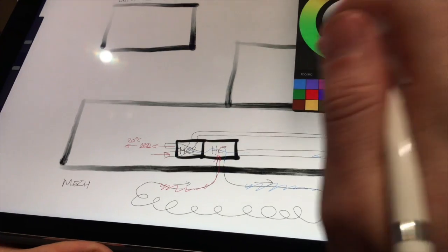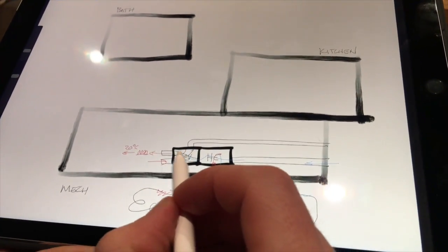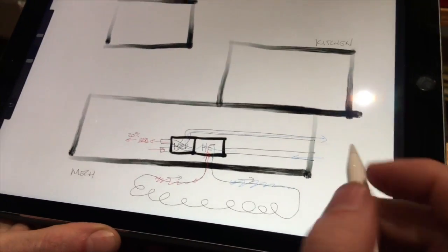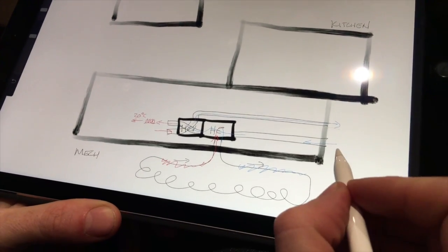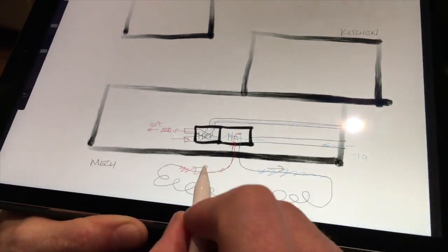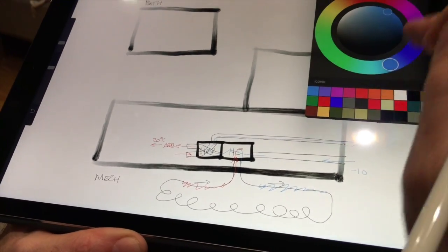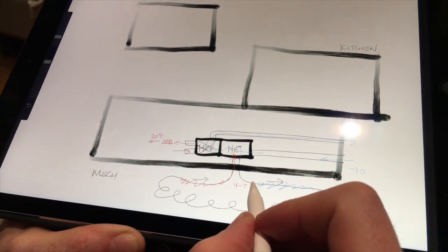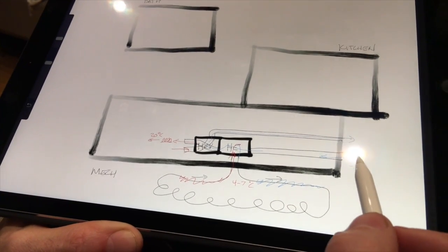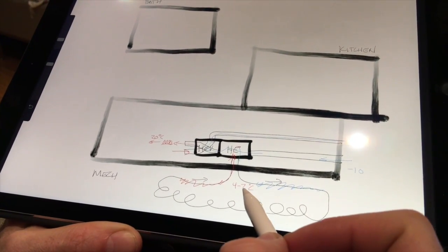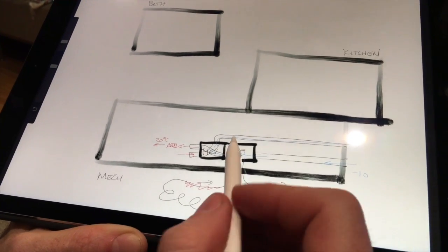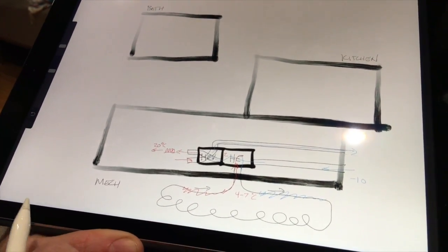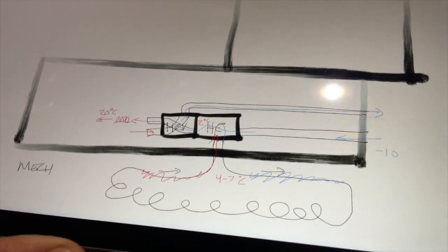And put some temperatures on the other intakes. After the stale air is leaving the house, it goes out, it's cold. These are not exact calculations, but let's say it's minus 10 outside. The ground is probably going to be, let's say, between 4 and 7 degrees Celsius. So minus 10 air comes across a heating coil at this temperature. We'll bring it up after it leaves the heat exchanger, probably to just above 0 degrees, let's say 2 degrees for the sake of argument, as it leaves the heat exchanger.